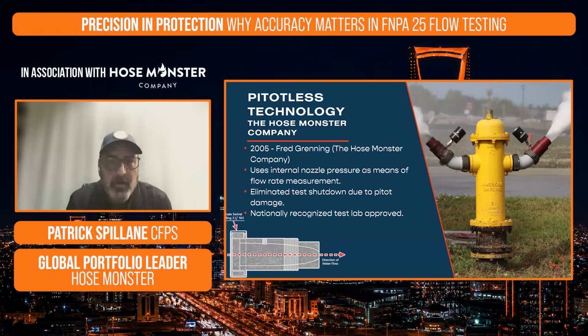And so it really all starts with our Hose Monster technologies, our pitotless nozzle technology. So at Hose Monster, we measure water flow very accurately, and a little bit differently than a lot of other components out there in the world. A lot of people are familiar with the pitot tube, the handheld pitot tube that really started it all. However, that pitot tube is difficult to use because the accuracy is questionable depending on how it's being applied by the technician. A pitot tube has to be put into the water stream at a very particular location to get an accurate measurement. We saw how inaccurate that was when we started our company about 30 years ago.